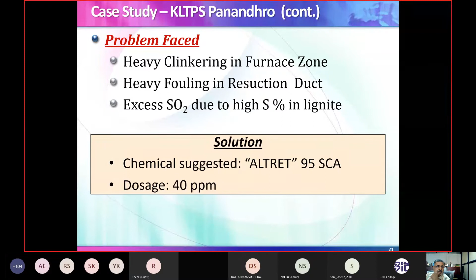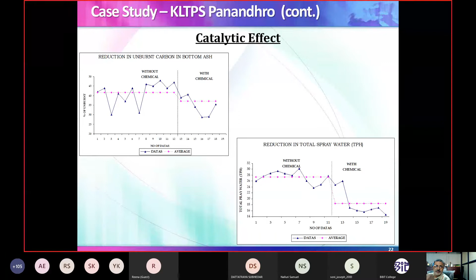You can see the result, reduction in unburned carbon in bottom ash. It has reduced from about 44% to somewhere about 37%, 36%. This shows that there is a catalytic effect in this additive. Similarly, spray water, which is normally sprayed on the superheater, shows a reduction. Earlier it was about 27.5 tons per hour. Now it has come down to about 18 tons per hour. So this reduction is associated with two factors, the catalytic effect plus the anti-fouling effect.